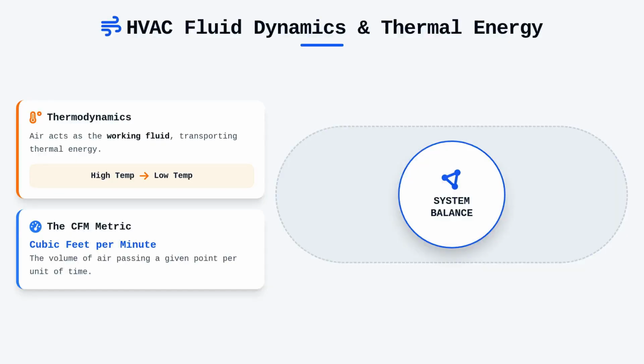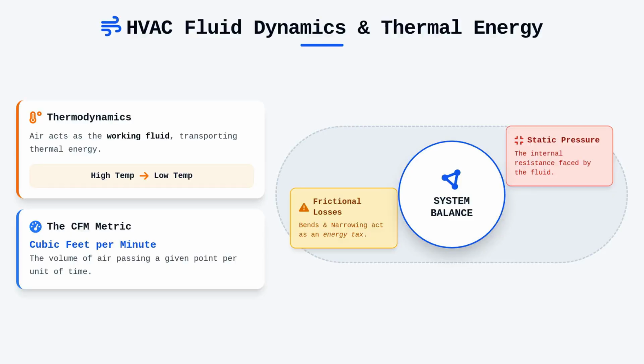However, volume alone tells an incomplete story, as we must balance it against static pressure, which is the internal resistance the system faces. Every bend, transition, and narrowing of a duct contributes to frictional losses, which act as a tax on the system's total energy capacity.